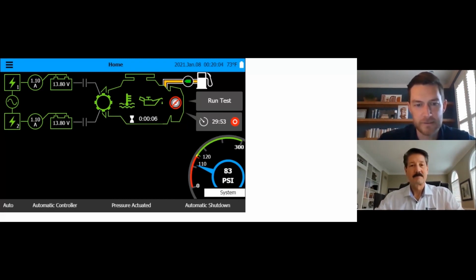Of course, the pressure would typically jump back up above that cutout point because you're running on a closed system, so you don't have to worry about it being below the cut-in point. And it's going to run for 30 minutes and shut itself down, and it's going to log it as a run test versus an auto start.